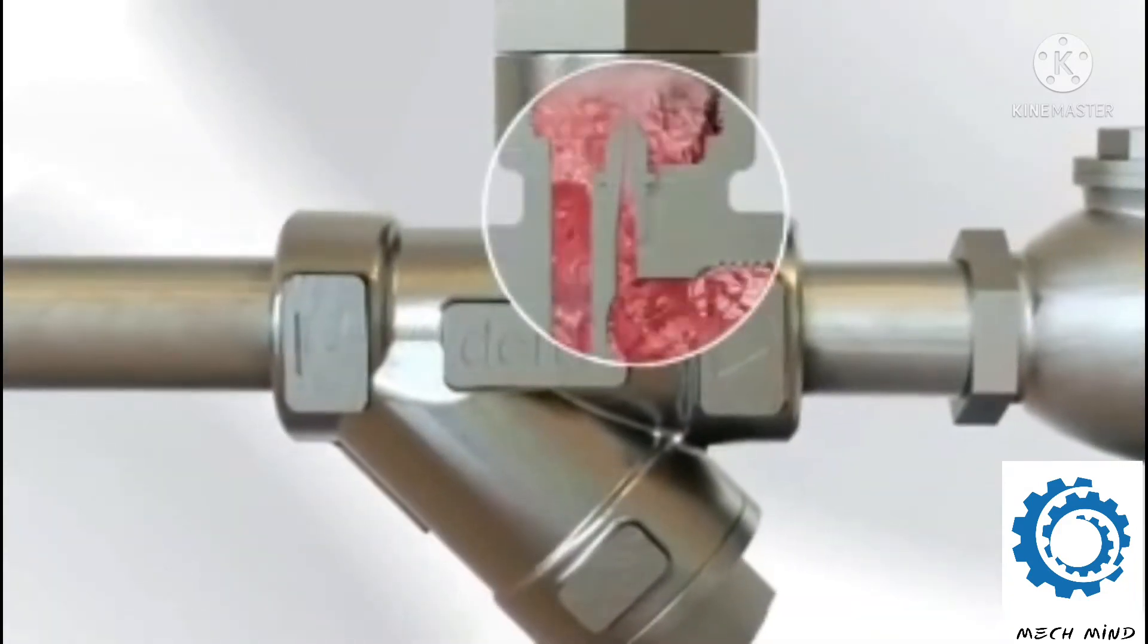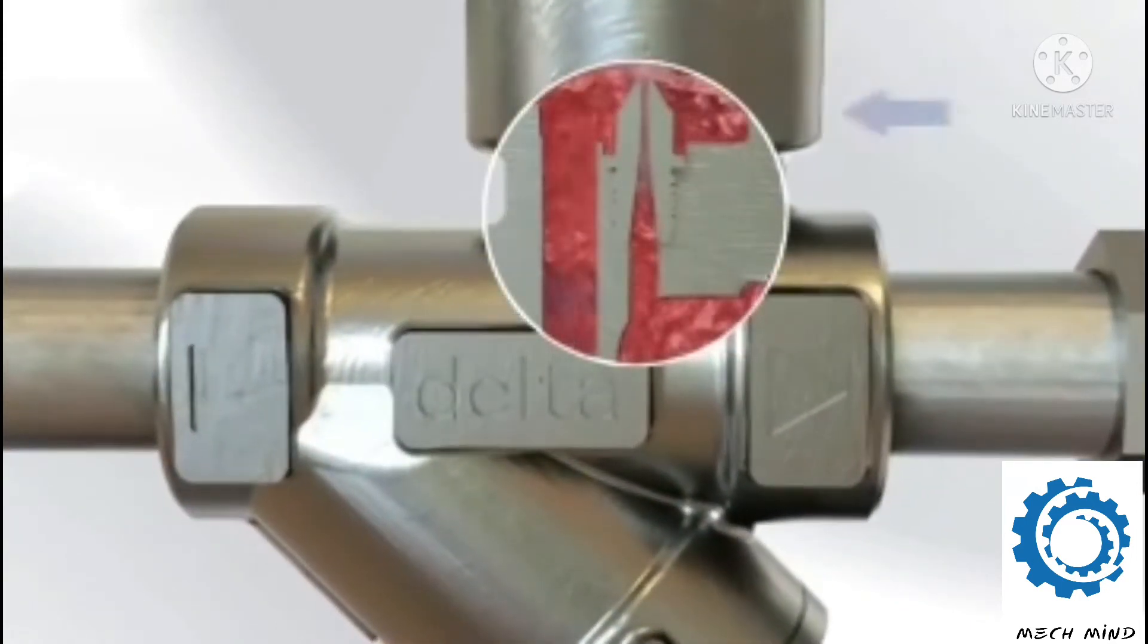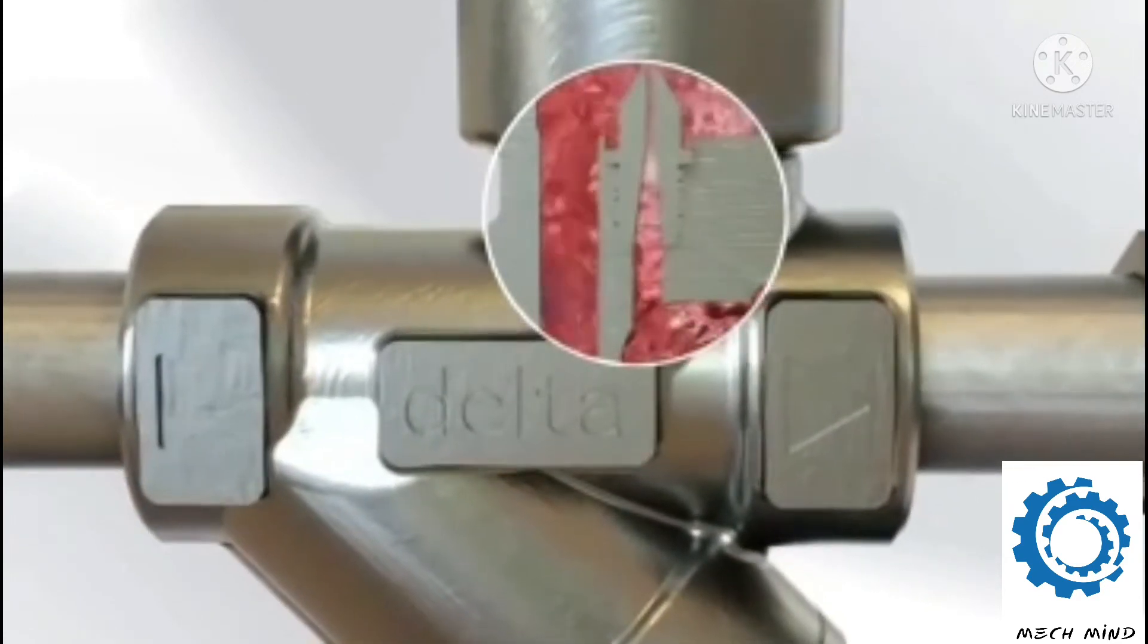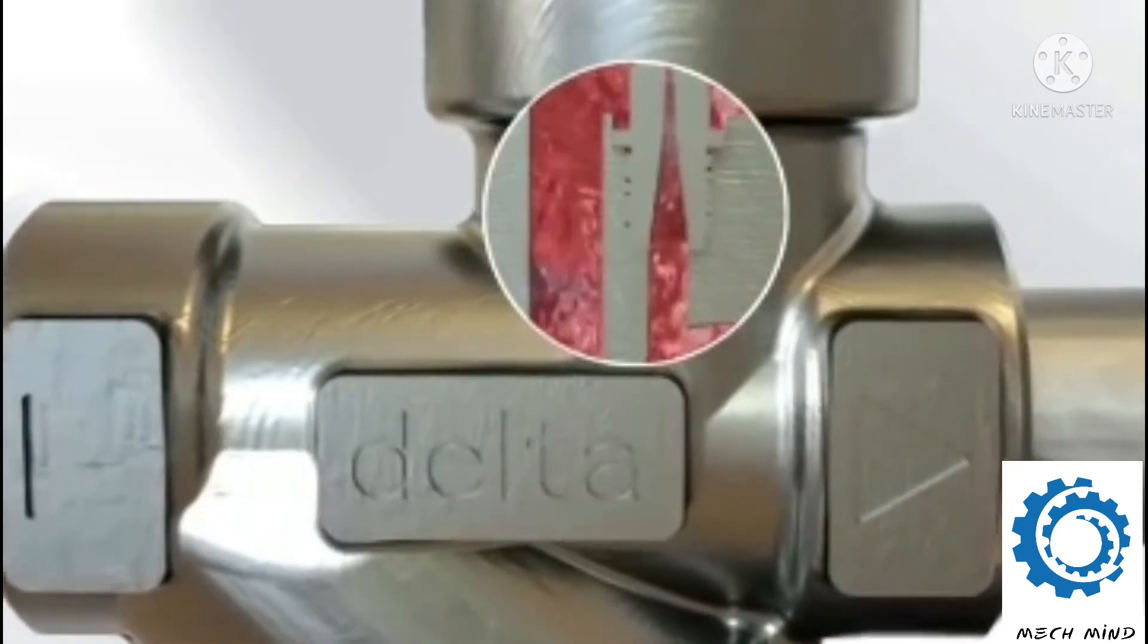As the pressure and load in the steam system vary, so too does the percentage of flash steam being created at the mouth of the venturi in the delta steam trap, which in turn allows the back pressure at the venturi to vary accordingly.